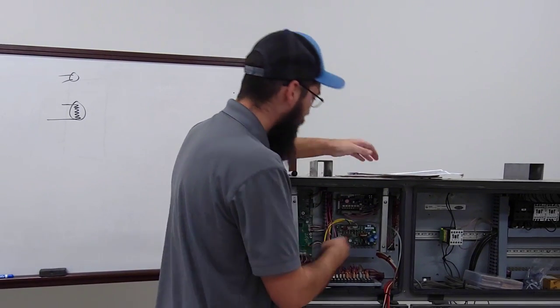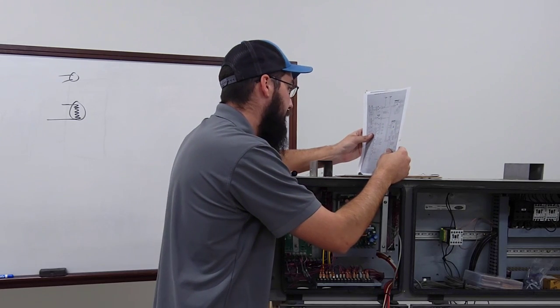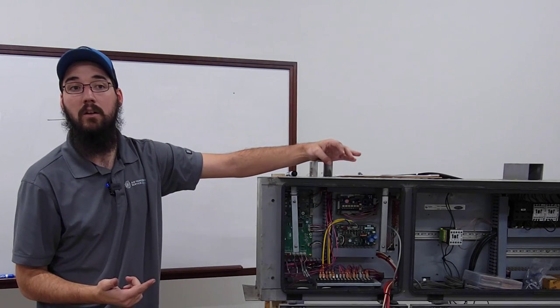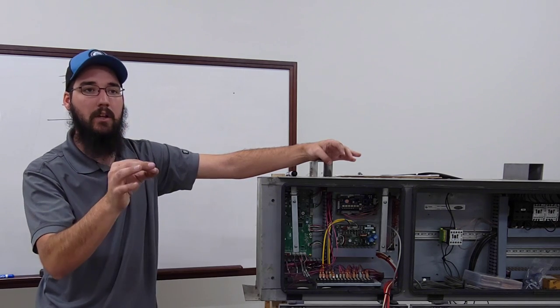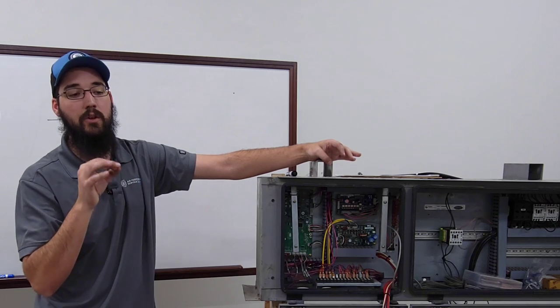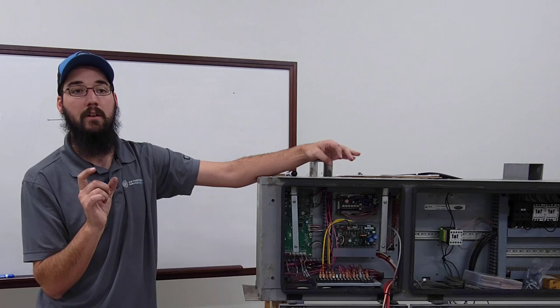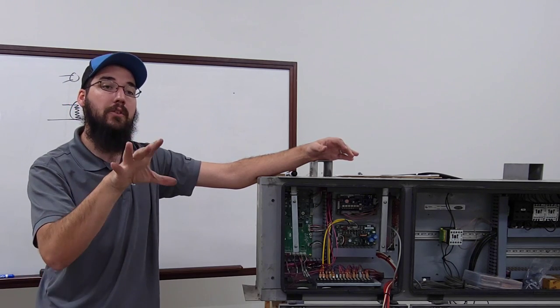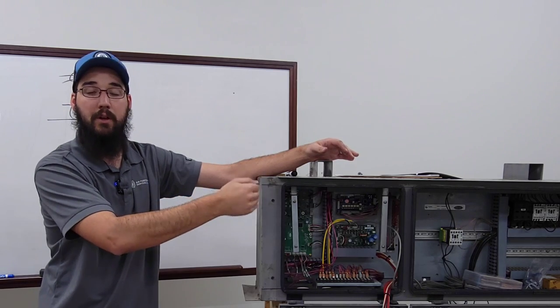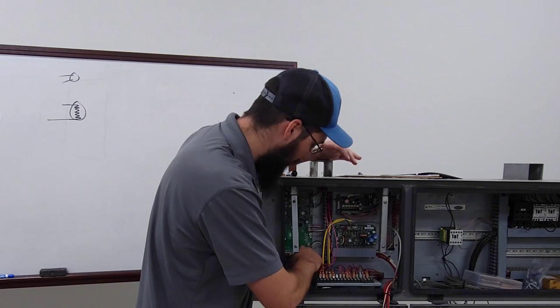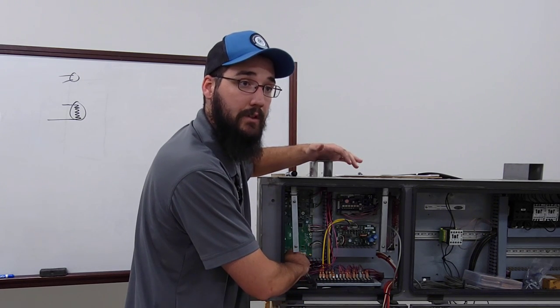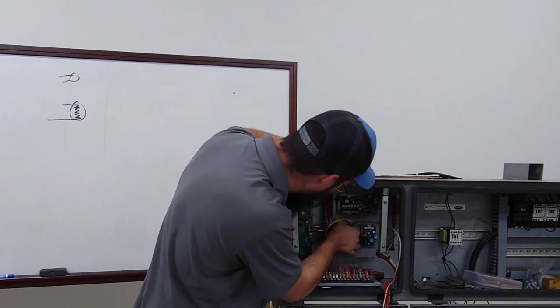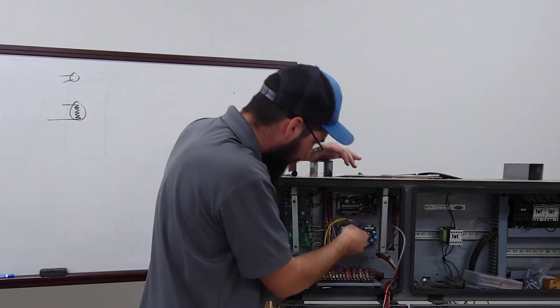Fluke is one I can highly recommend — they have an excellent set of little black long needle points, and they've got insulated ones. You would test DC volts between the white and the black, and then you'd switch over to the appropriate voltage and read between the red and the black to see if you're getting power and if it's outputting the DC signal. In some cases you can go to the transducer itself and it might have a voltage rating on it — though whether it's faded or covered in oil is a different story. If the other transducers appear to be working and it's isolated to one, use them as examples — test between all of them to see if they're all outputting the same voltage. That's a real metric you can use.